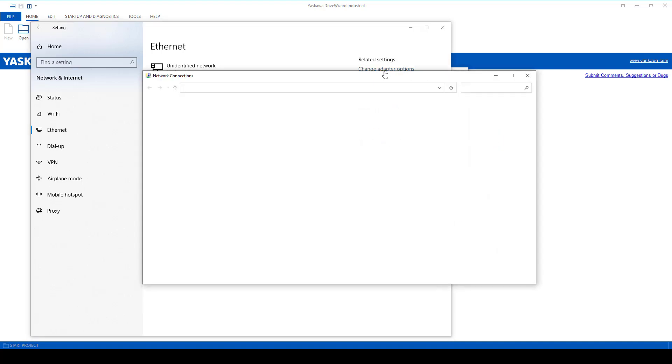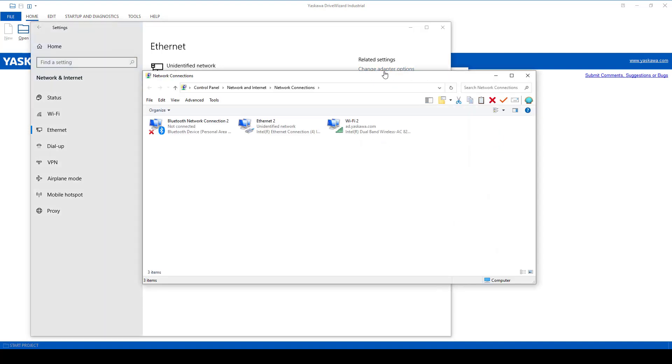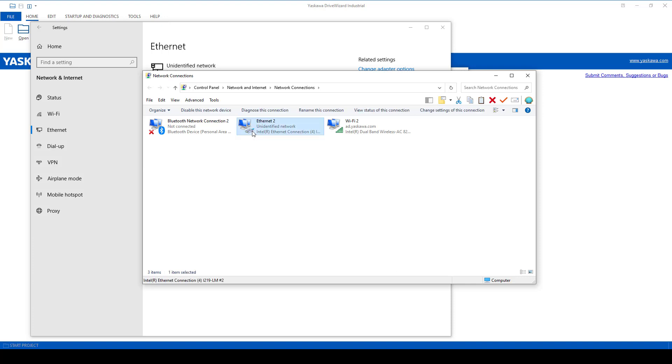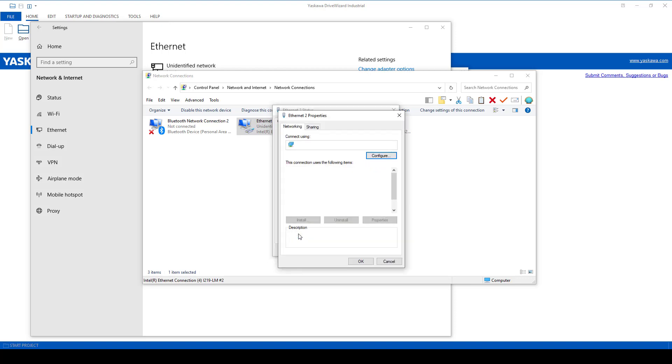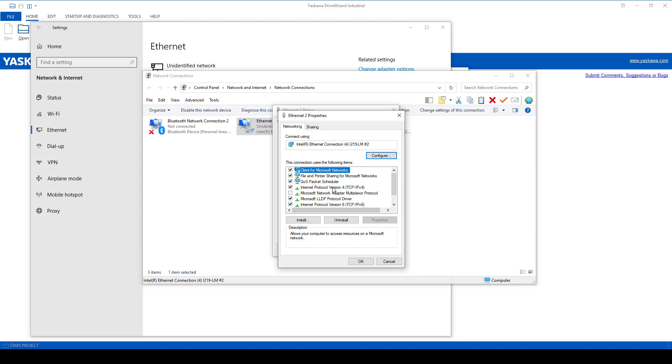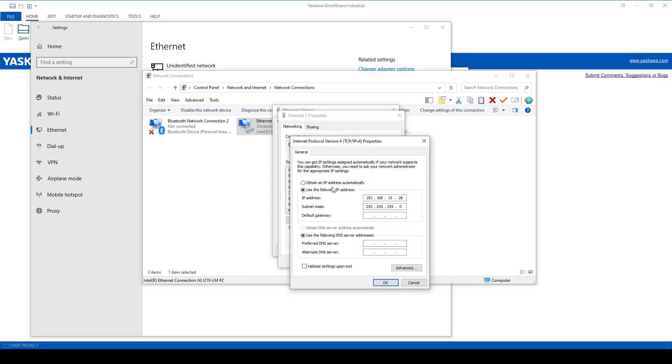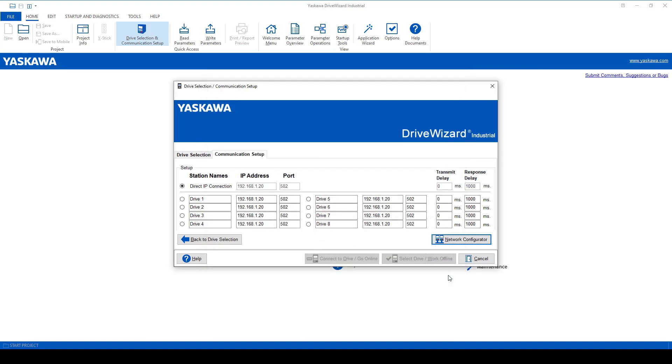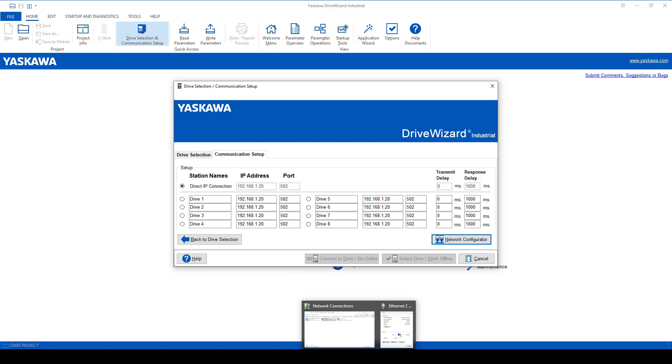You will see the connection you have shown, but it's unidentified. Double-click on it. Select Properties from the pop-up, and then select the IP version 4. Select the radio button to set the static address. This is where you will set the IP address. Verify the IP address of the drive wizard and set the first three values in the Windows setting.